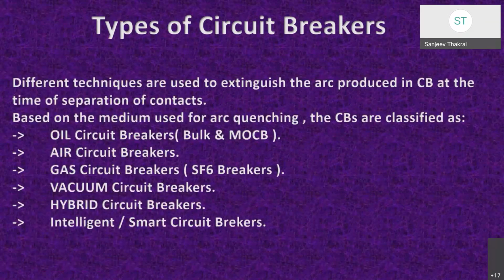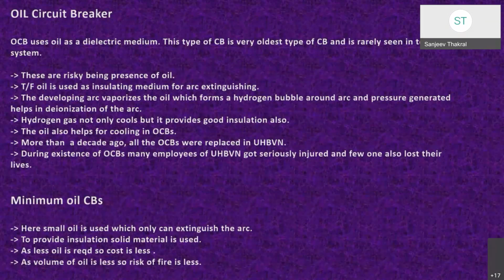Now, depending upon the techniques or the arc extinguishing medium, circuit breakers are classified into oil circuit breakers, bulk oil and the MOCB, air circuit breakers, gas circuit breakers, vacuum circuit breakers, hybrid circuit breakers, and intelligent circuit breakers. Oil circuit breakers. Oil circuit breakers use oil as a dielectric medium. This type of circuit breaker is the oldest type and is rarely seen in today's system.